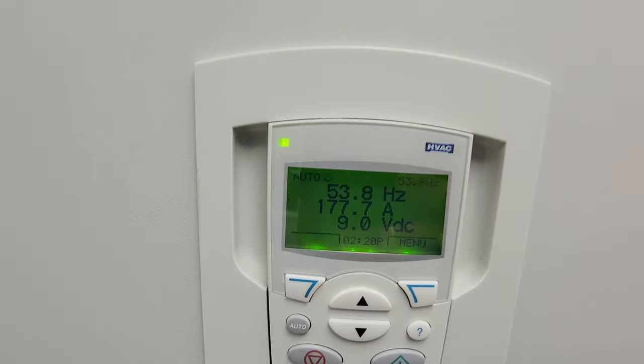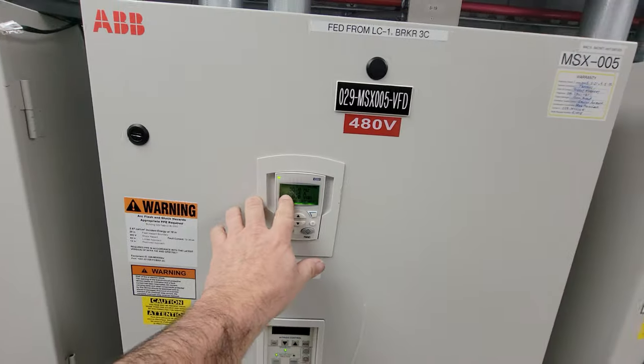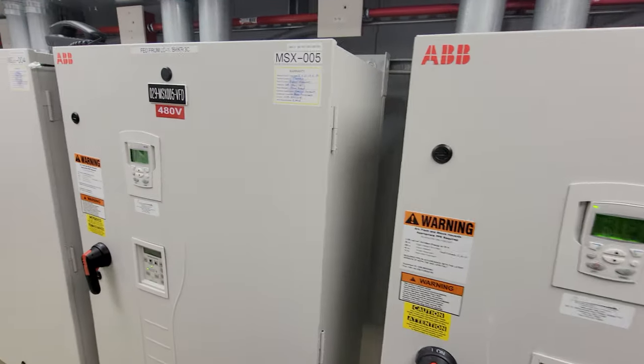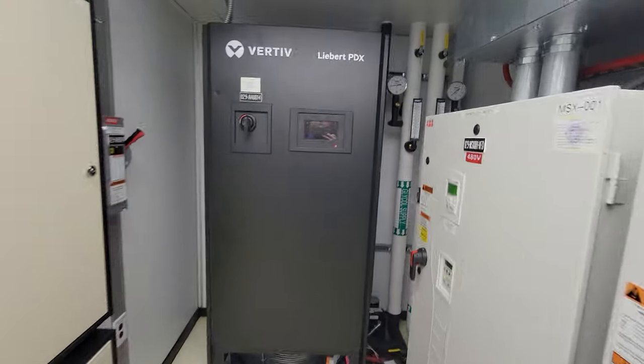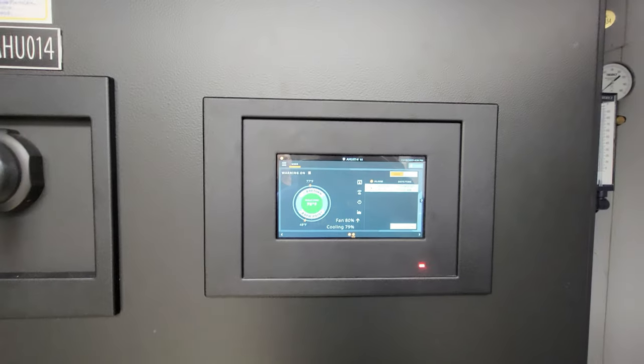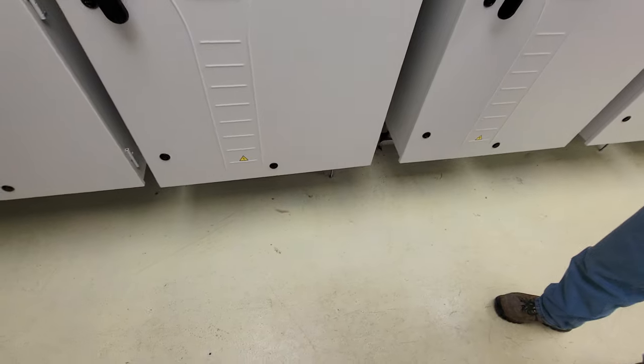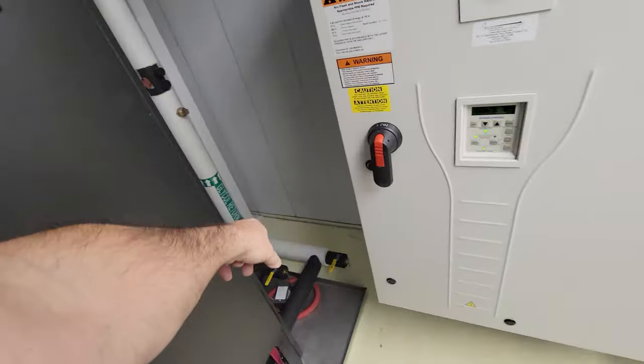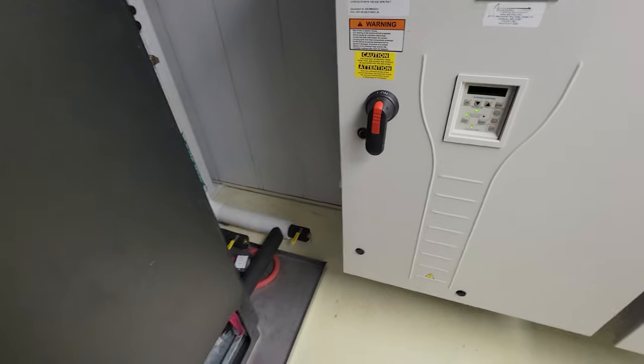We're running 176 to 190 amps. There's a lot of warmth here — that's why we have the two Lieberts. They're just for the drives. Are they blowing it straight down? Yep, straight down. Is this for the condenser? It's chilled water — there's a glycol system from the condenser. So it's a water-cooled condenser? Yep.